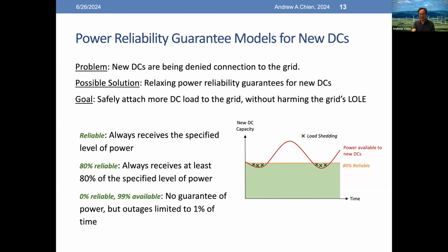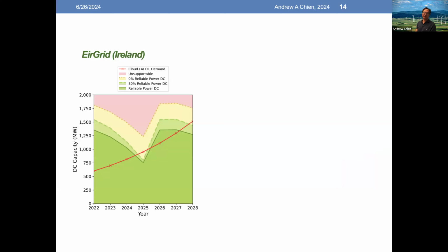And then the third, which is the most aggressive, is let's just say you don't guarantee any reliability, that you may have outages as much as 100%, but the outages are limited in time to just 1% of the time. So that's 2 nines or something like that, reliability, or many hundreds of hours a year of outages. So let's consider these two less stringent reliability guarantees and see how that changes the balance.